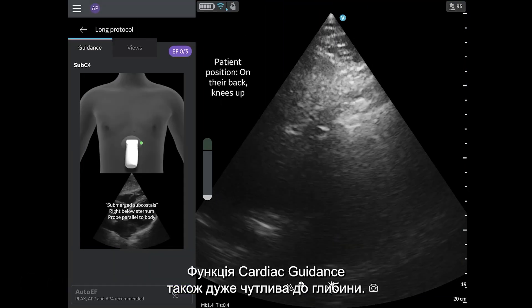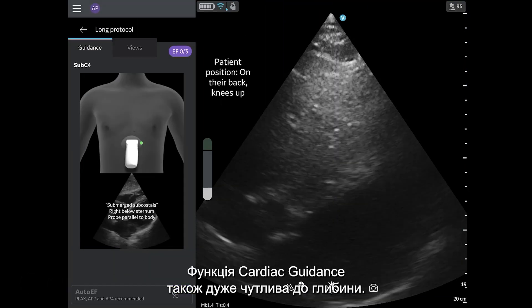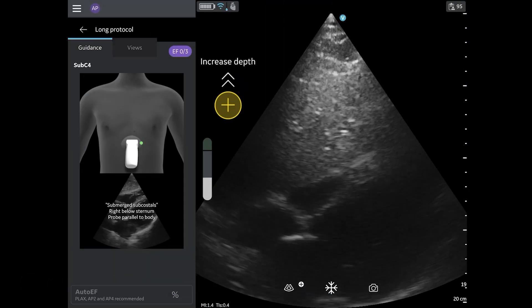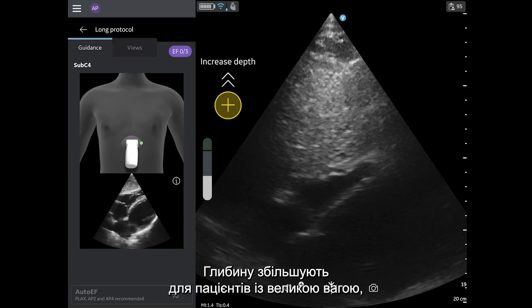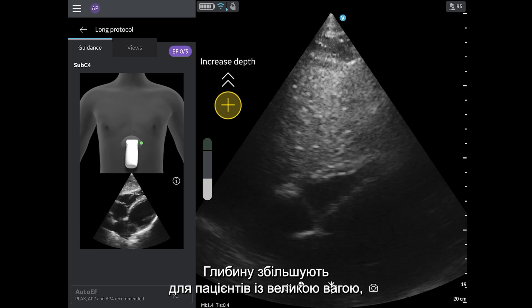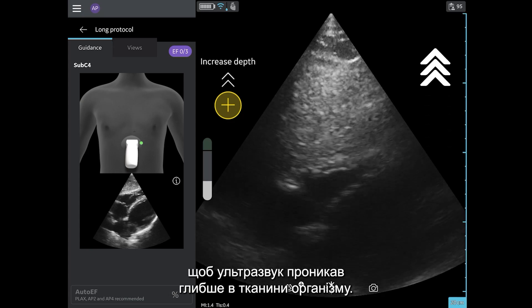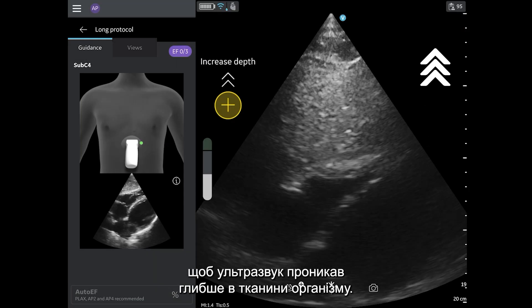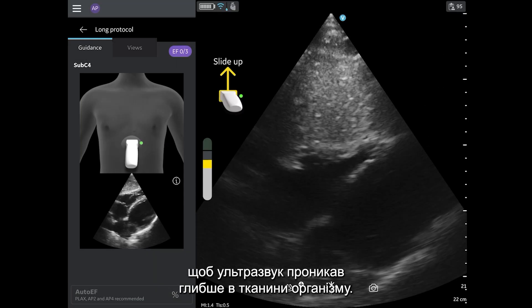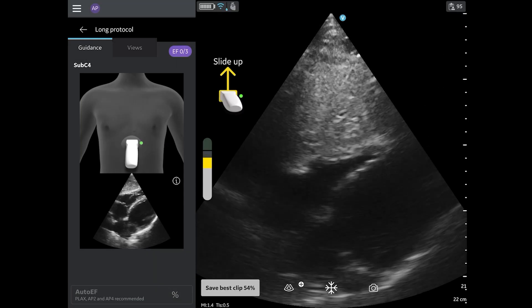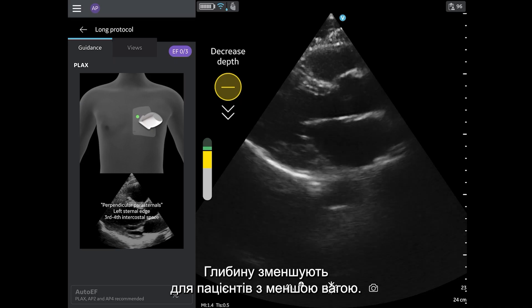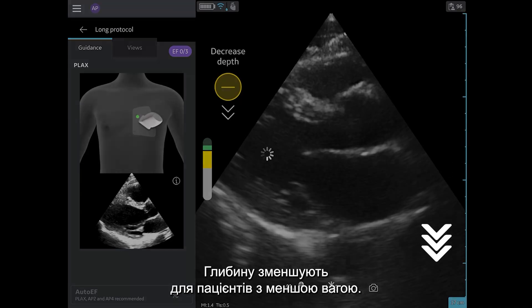Cardiac guidance is also very sensitive to depth. For larger patients, depth may need to be increased so the ultrasound can travel deeper into the patient. For smaller patients, it may need to be decreased.